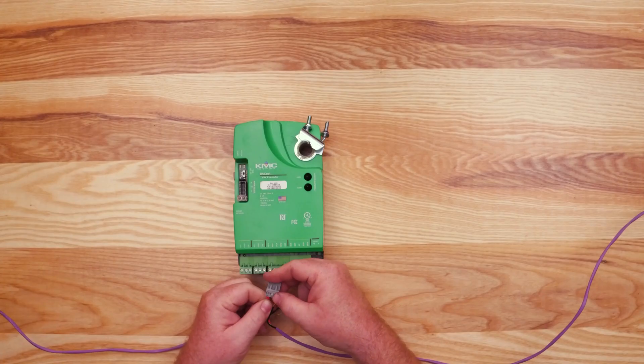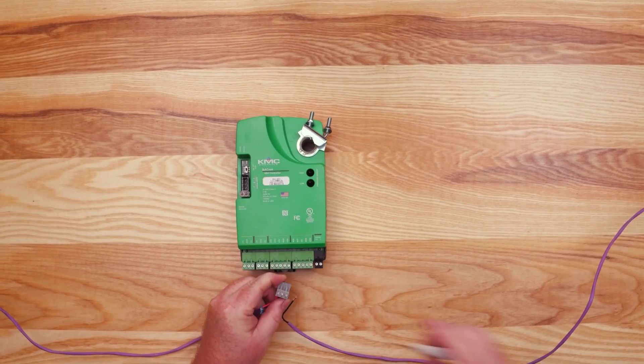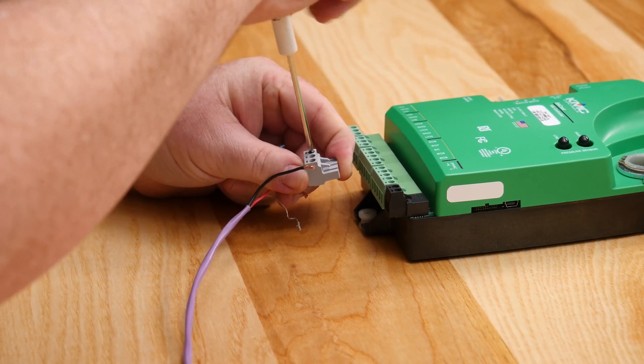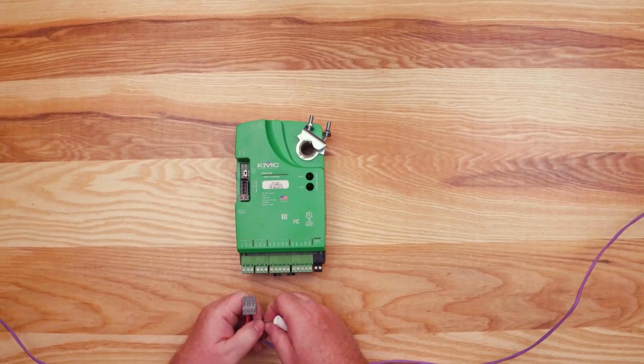Assuming this controller is in the middle of the network, start by connecting the negative A wires in parallel with all other negative A wires on the network. Likewise, connect the positive B wires in parallel with other positive B wires on the network. Connect the shields of the cables together in each device.